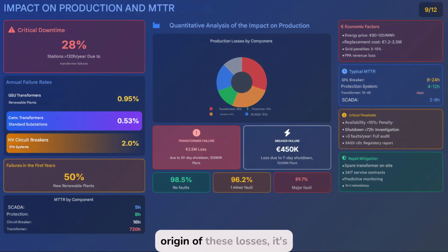To better understand the origin of these losses, it's worth reviewing the annual failure rates by component. GSU transformers, common in renewable energy plants, have a failure rate of 0.95%, while in conventional substations, this figure drops to 0.53%. However, HV circuit breakers, especially in SF6 systems, reach 2%, reflecting their vulnerability under demanding operating conditions. If we focus on newly built renewable energy plants, the situation is even more delicate. Up to 50% may fail during their first years of operation due to technical immaturity, design errors, or poor installation conditions. These failure rates have a direct correlation with production losses.